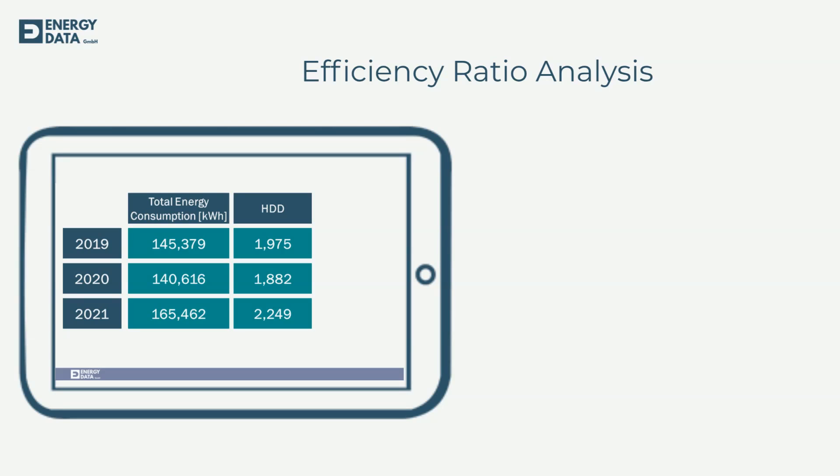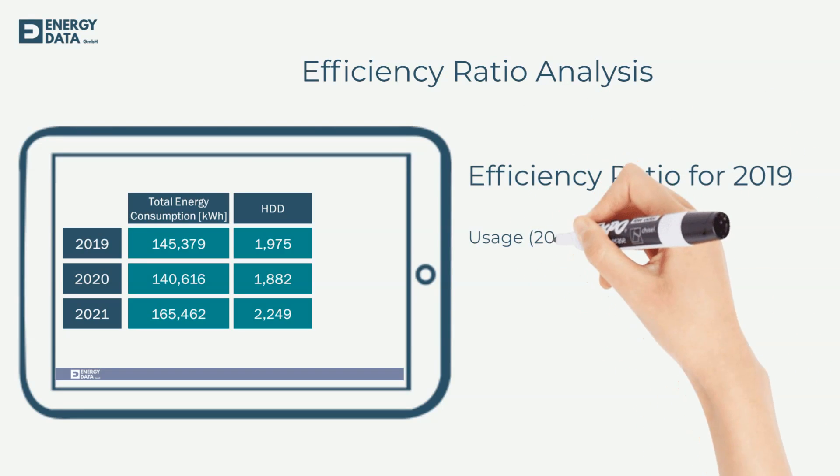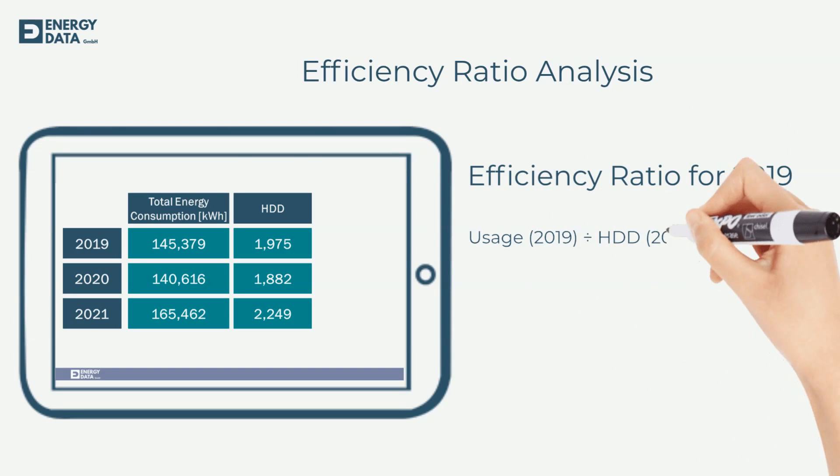To calculate heating degree days you need to know the base temperature for heating of your building. Combined with your location you can easily get the accurate degree days with our degree day calculator for free. To get the efficiency ratio for each period you just divide your usage by the sum of degree days in that specific period.